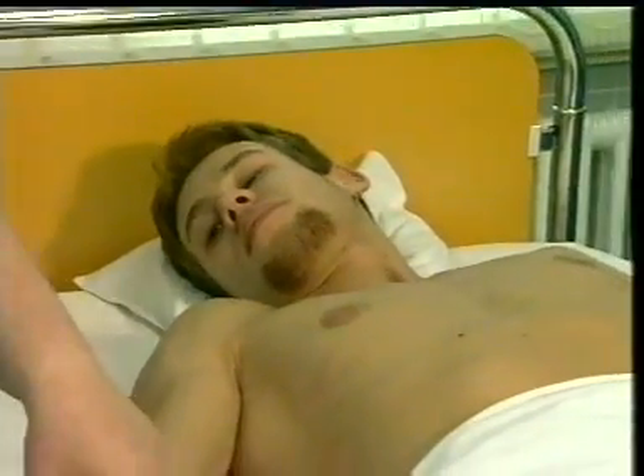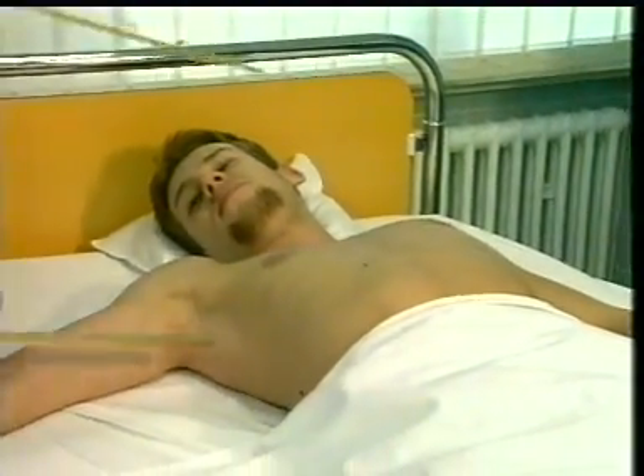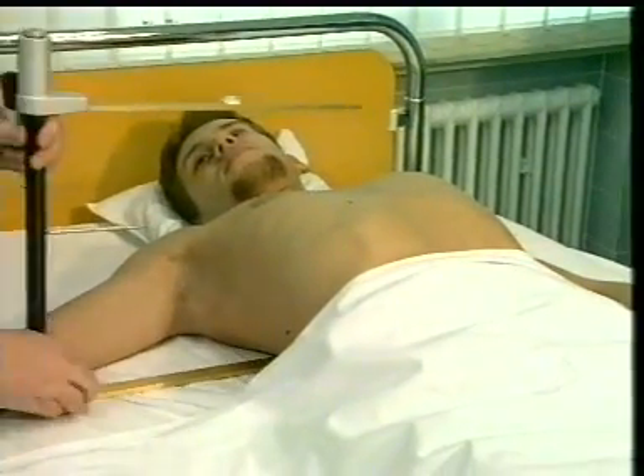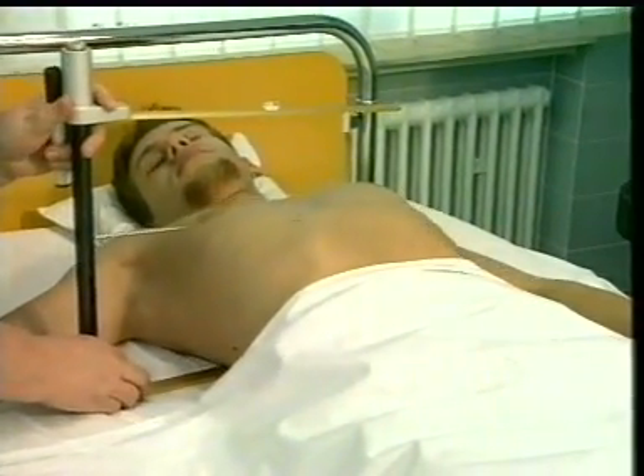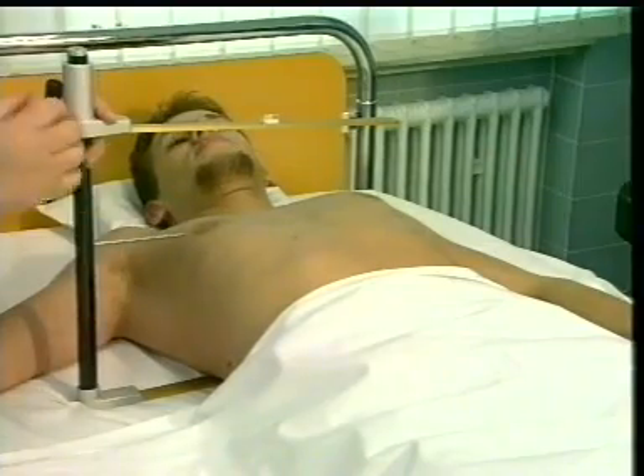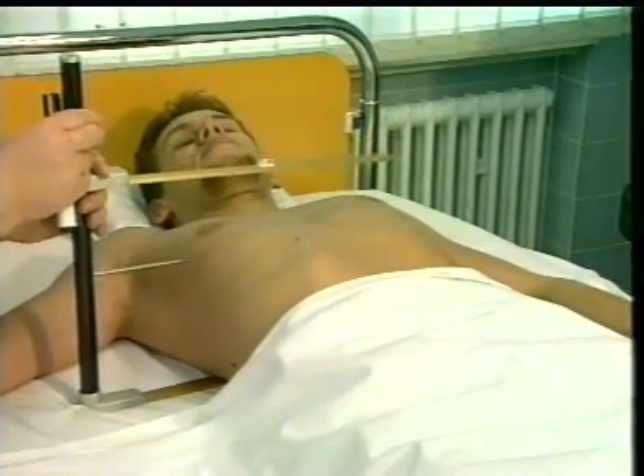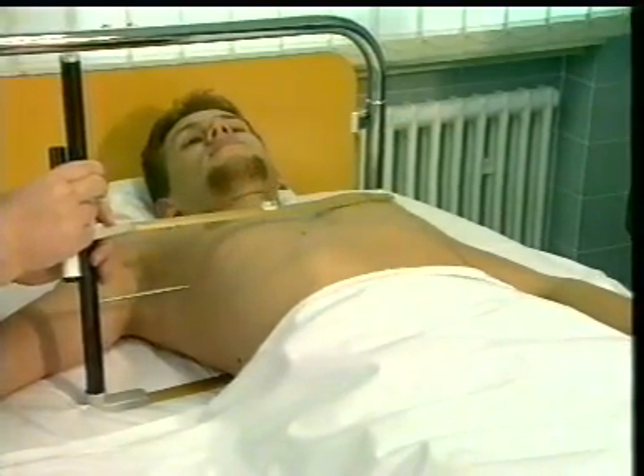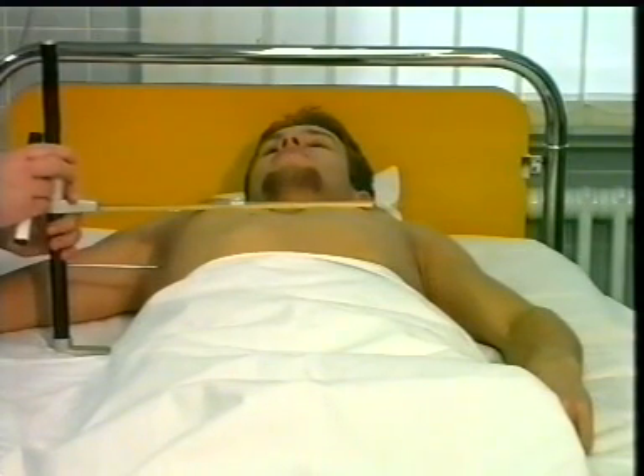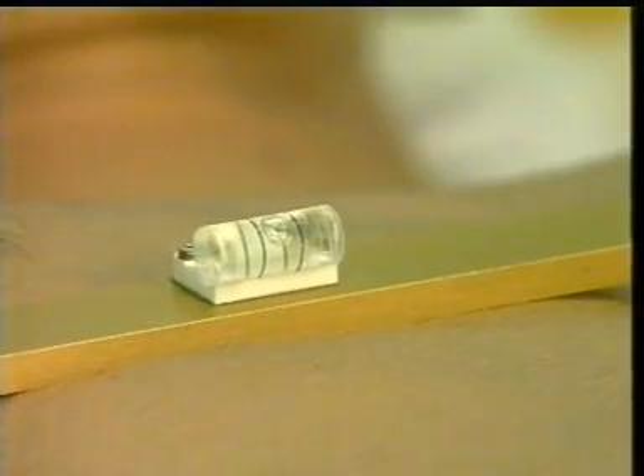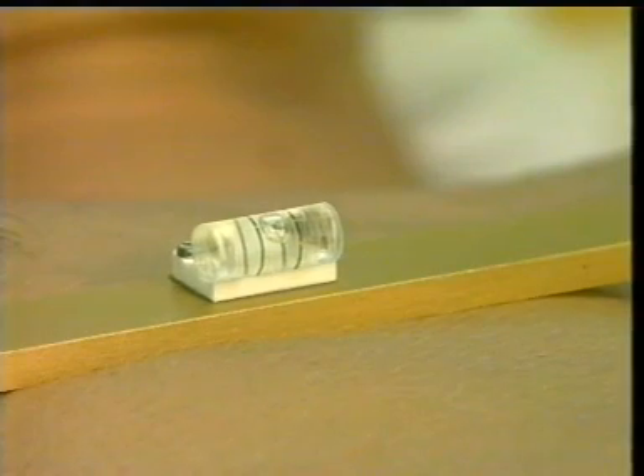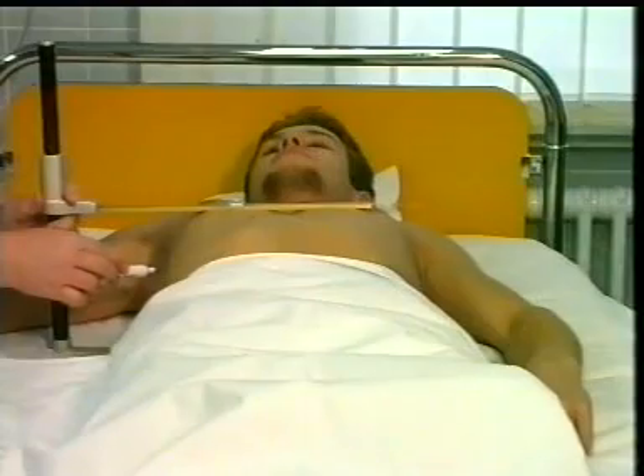The thorax sliding caliper is used to set the exterior 0 point. The lower arm of the caliper is inserted 3 to 4 fingers above the xiphoid process of the sternum between the patient's back and the surface on which he's lying. The upper arm of the caliper is placed on the upper thorax wall and brought into alignment. The steel pointer indicates the 0 point, which is then marked with a water-resistant marker.